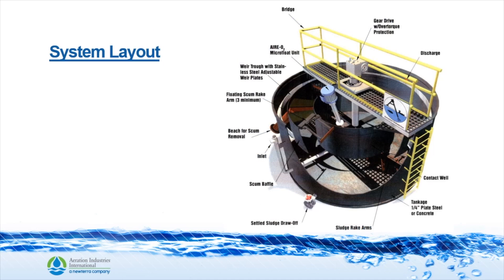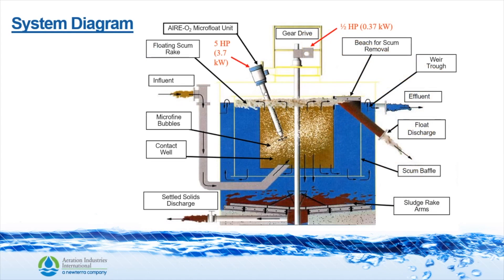Here is a 3D rendering of our DAF unit. This is a system diagram of our dispersed air flotation. On the left, you can see the influent comes in and enters into the contact zone where the microfloat unit adds micro-bubbles. Then we have a skimmer arm and a scum beach where we remove the floatables. On the bottom, we have a solid scraper to dispense of the heavier solids. And on the far right, you can see the clear effluent leaving the unit.